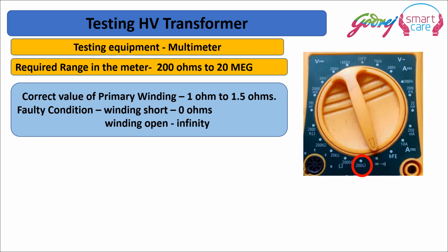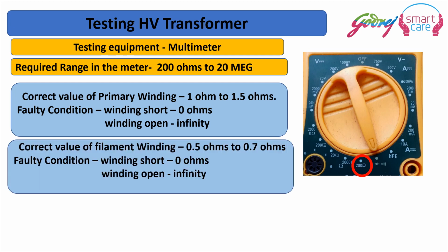That means somewhere the winding is short. Or if they show open, OL or infinity, then that means the winding is open. So for the filament winding, the secondary, there are two windings. One is the filament winding and the second winding is the step-up winding. For the filament winding, the resistance should be 0.5 ohms to 0.7 ohms. Very little resistance. The faulty condition again is for winding short it is 0 ohms and winding open it is infinity.